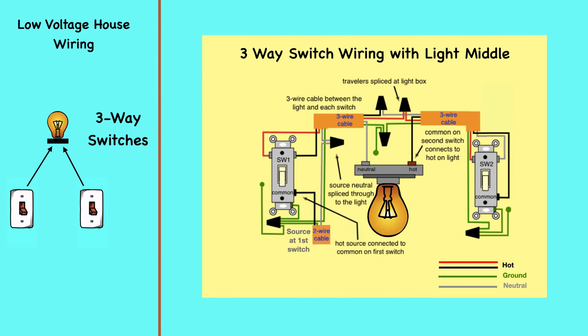The power source in this circuit is at the first switch, and the light fixture is located between switch number one and switch number two. A three-wire cable runs between each switch and the light fixture. The hot source wire is connected to the common terminal on switch number one, and the common terminal on switch number two is connected to the hot terminal on the light. The traveler wires are spliced in the fixture box to run between the traveler terminals on the switches — they are not connected to the light.